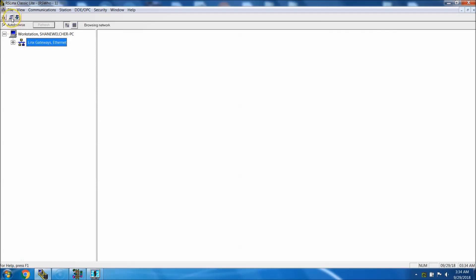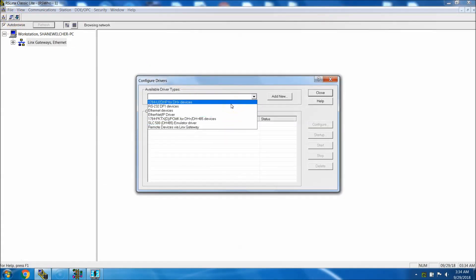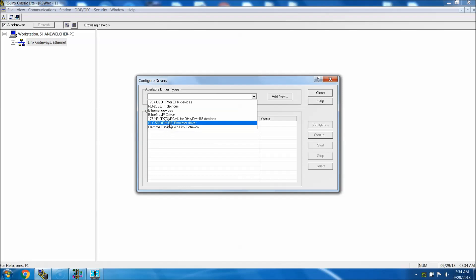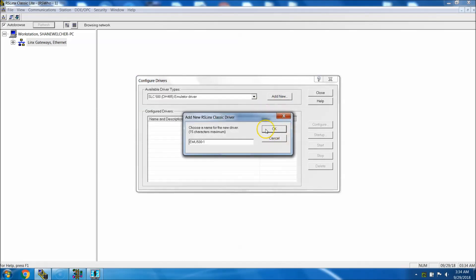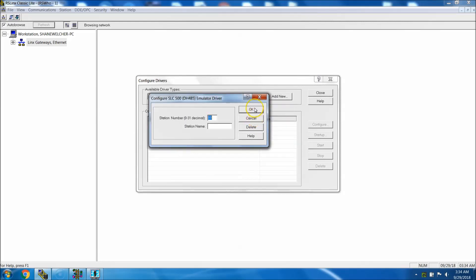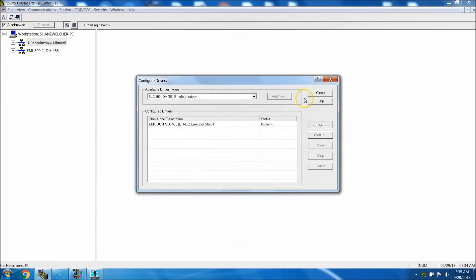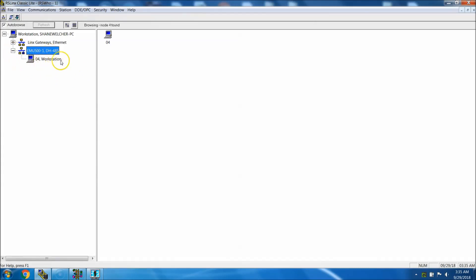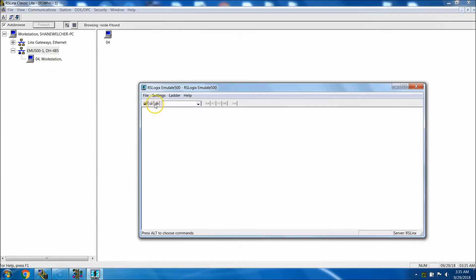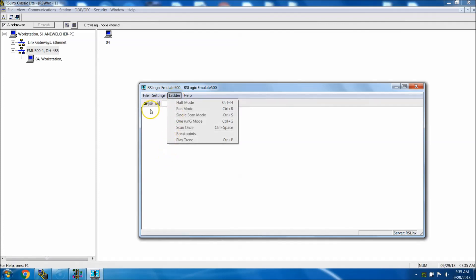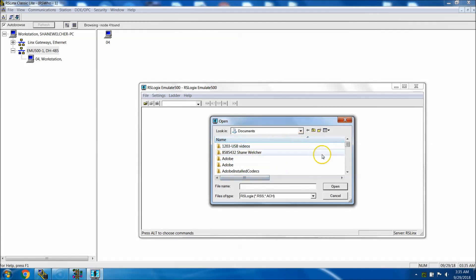Now we want to go into RSLinx Classic and go to 'Add Drivers'. You can add the SLC 500 Emulate driver — add it, and this will be 'EMU500-1'. You can pick your station number; I like to put my station number at something like 4 just to get it out of the way. Right now you have nothing in there but your workstation — your computer is going to be your processor in the emulator.